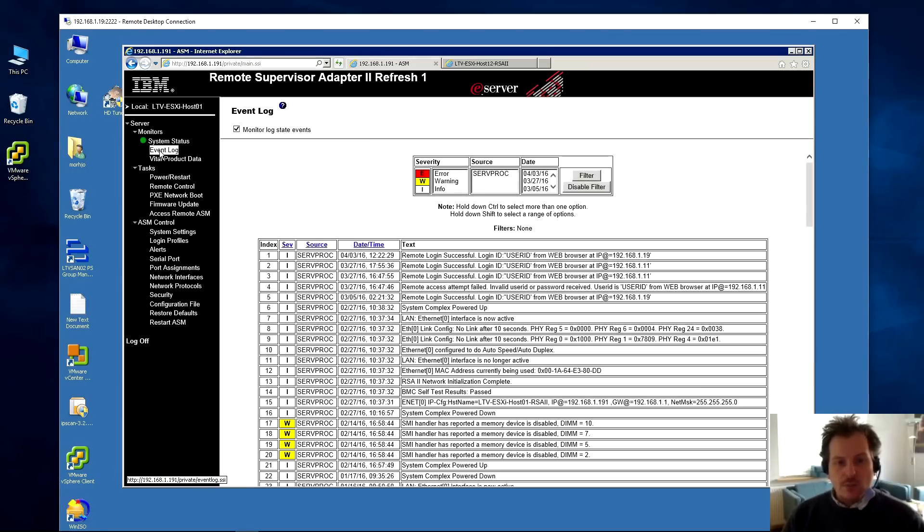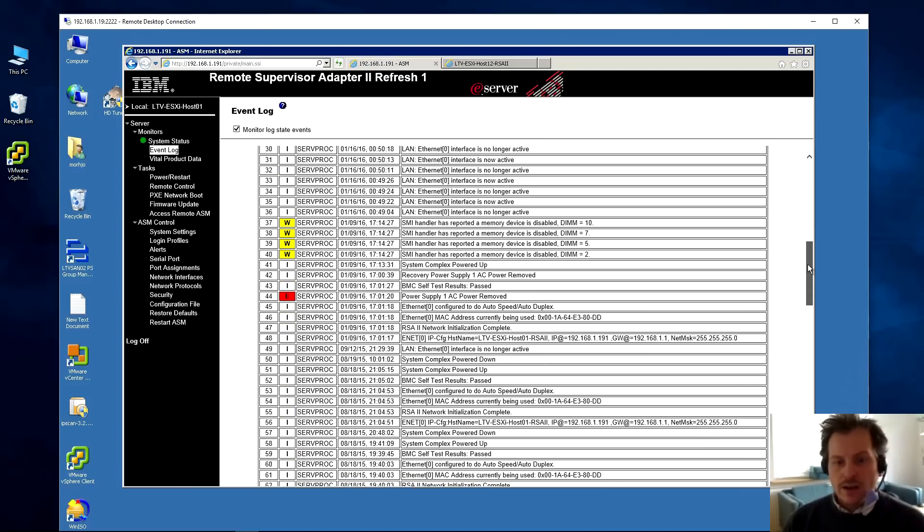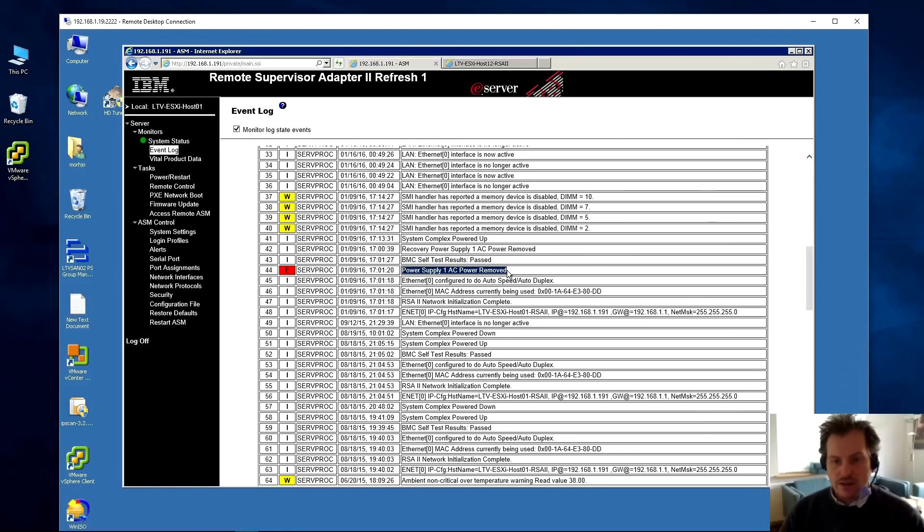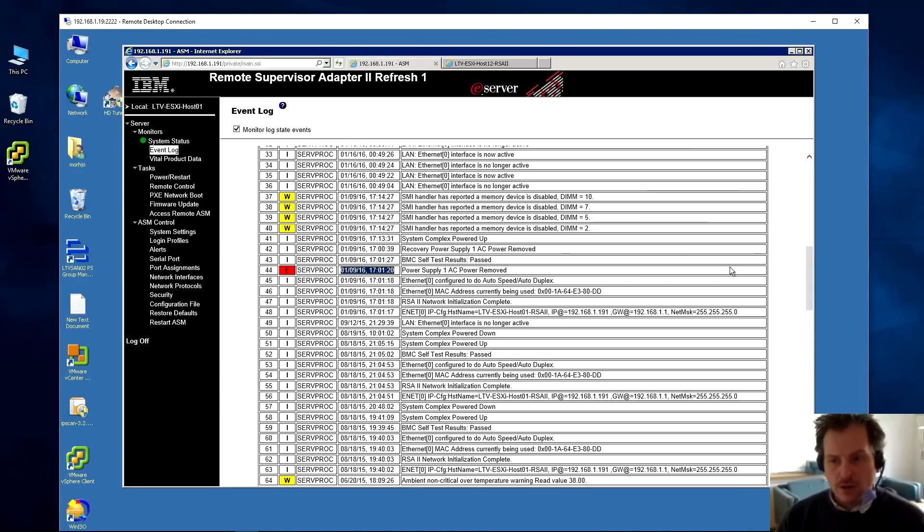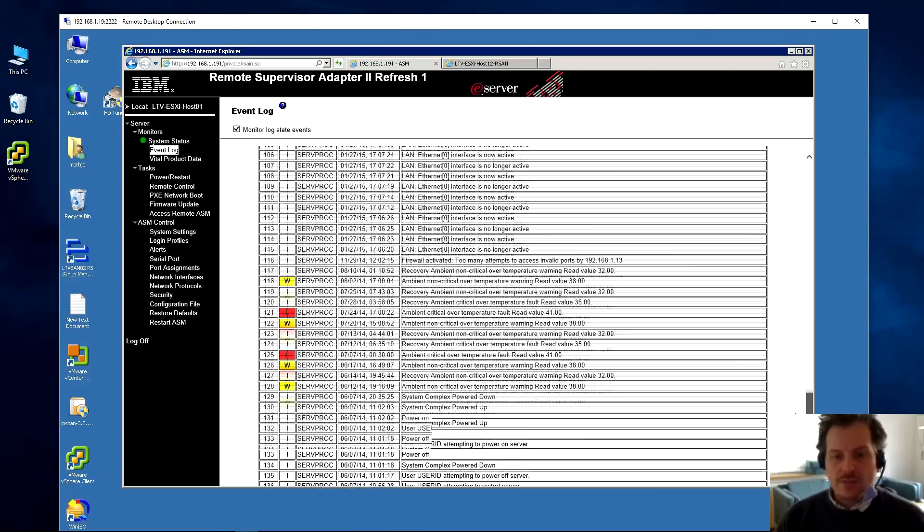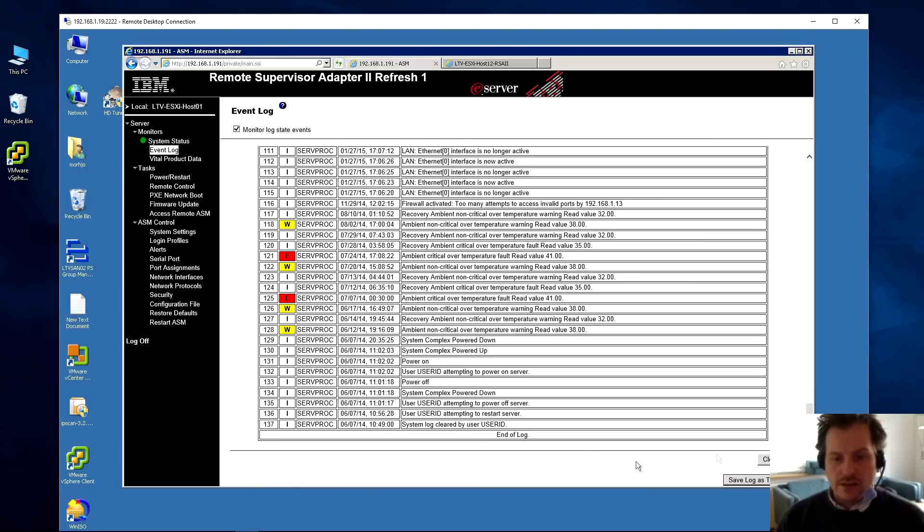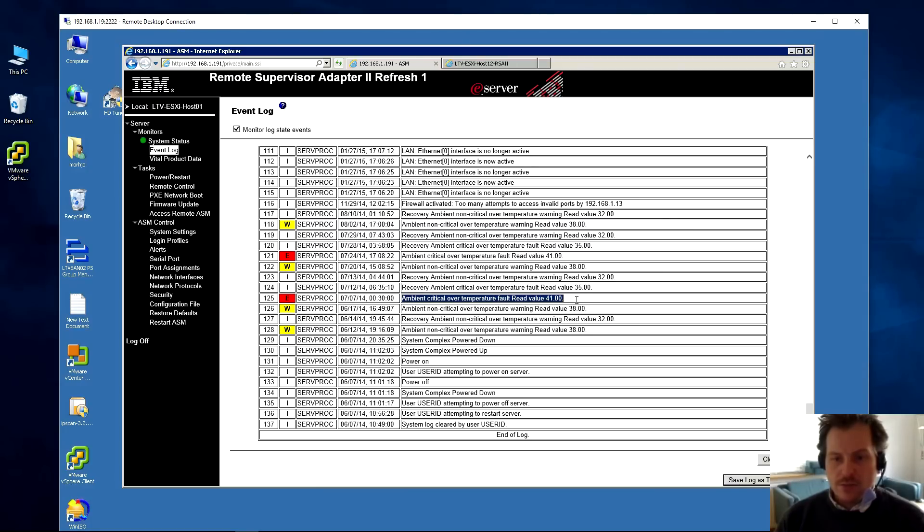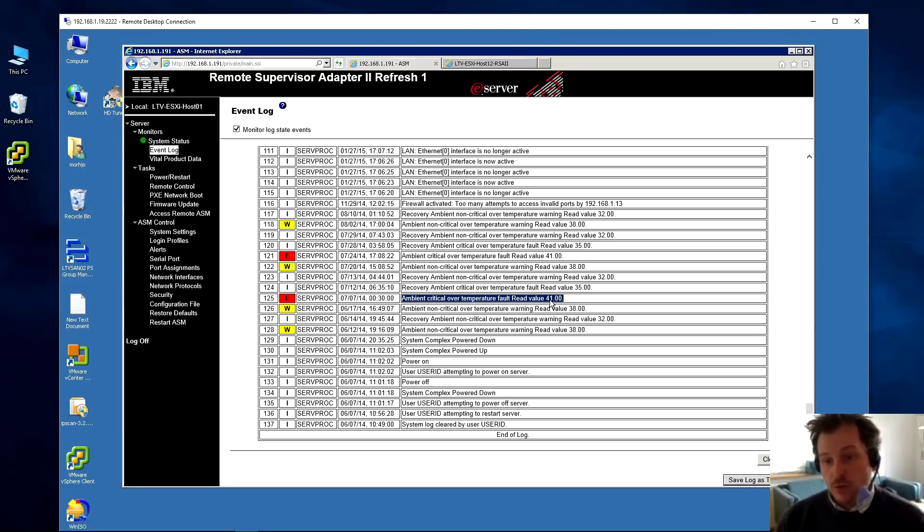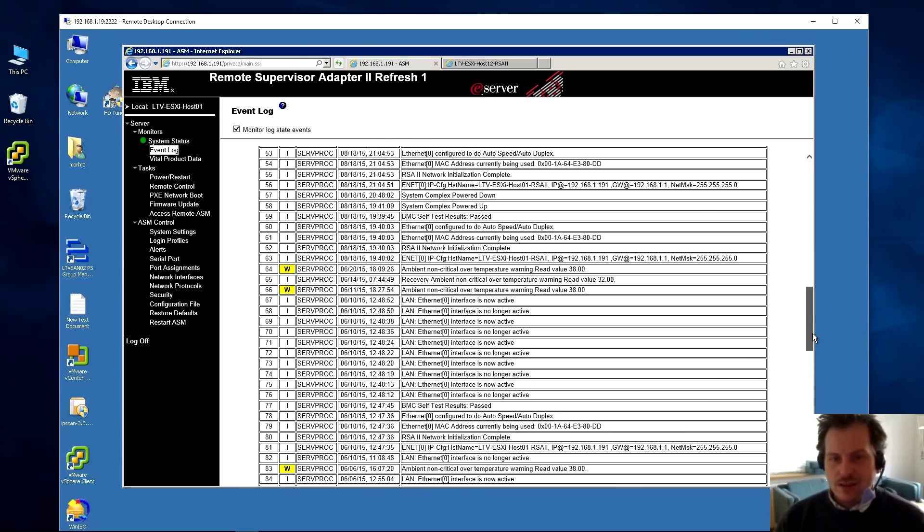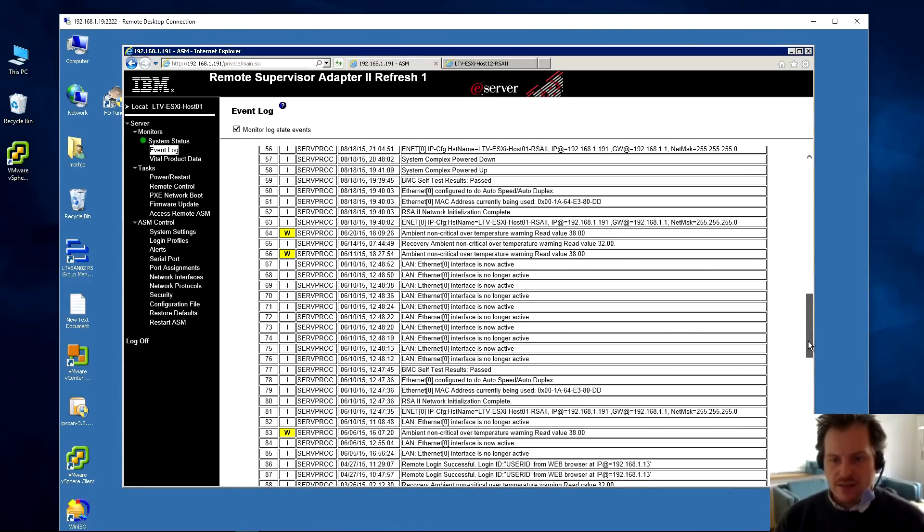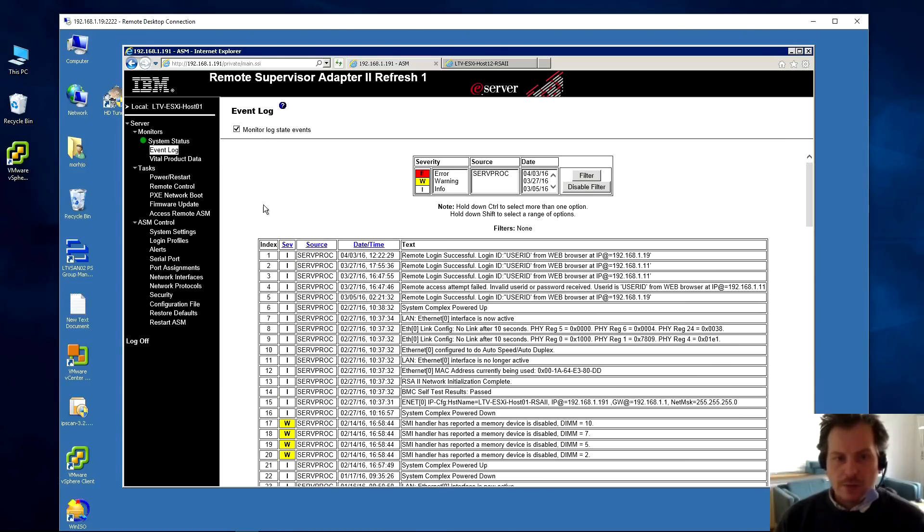Then we have a system log. It tells me what the system has been up to. I can see I have power supply one disconnected at some time on 9th of January at 5 o'clock. It has a nice big log with a lot of data. It seems I haven't cleared this since summer 2014. I can see I've had some heat issues - critical temperature here, 41 degrees. The server probably shut down at that time. I had another critical temperature some days after. The server will shut down by themselves if the temperature comes over 41 degrees. I could clear the log, but as long as it's not complaining the log is full, it's often nice to have things like this to look at. I'm gonna keep it.